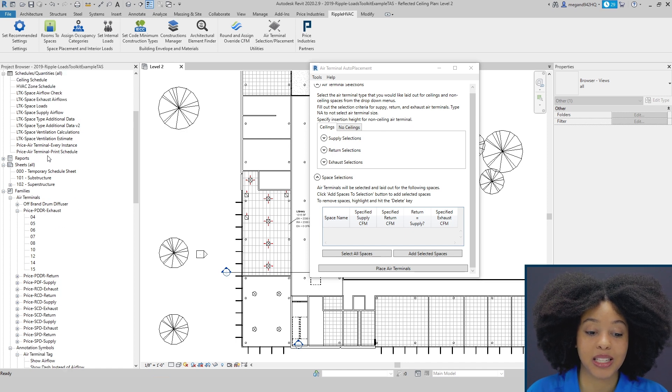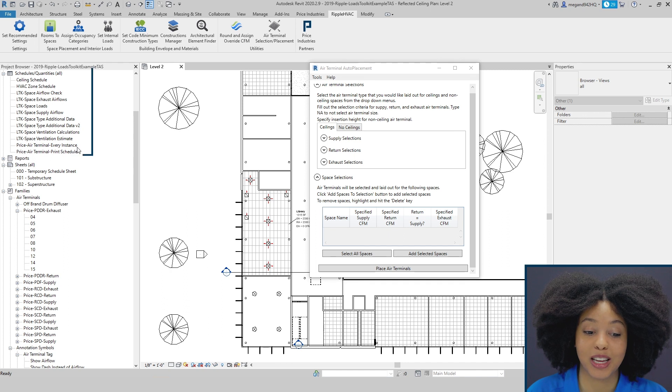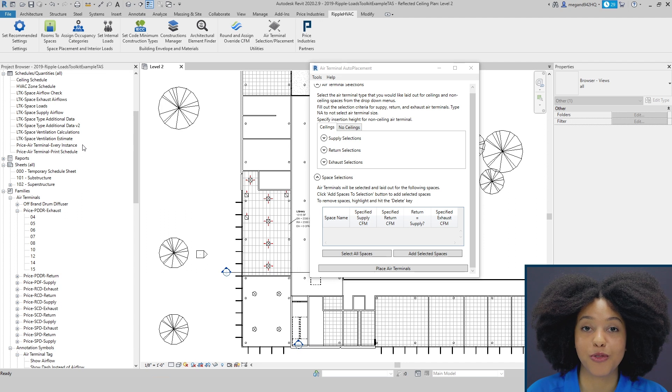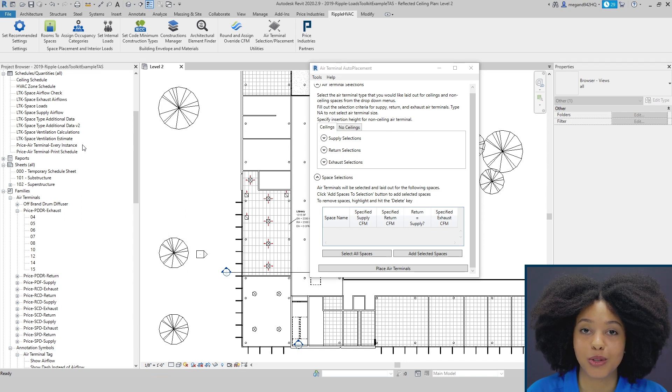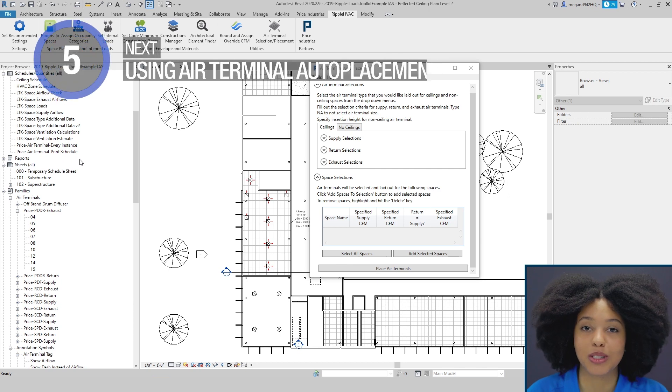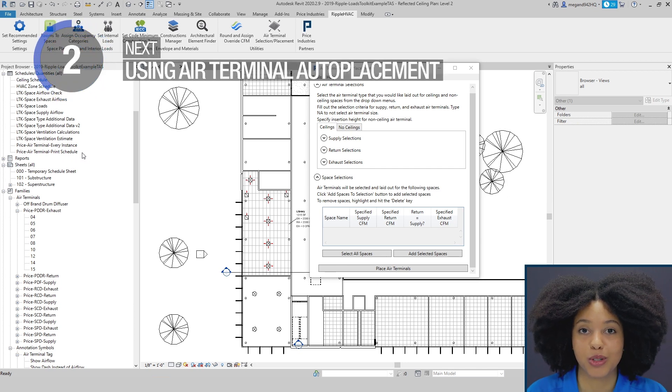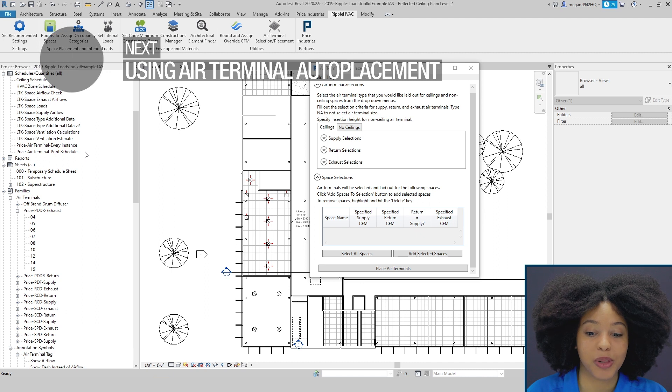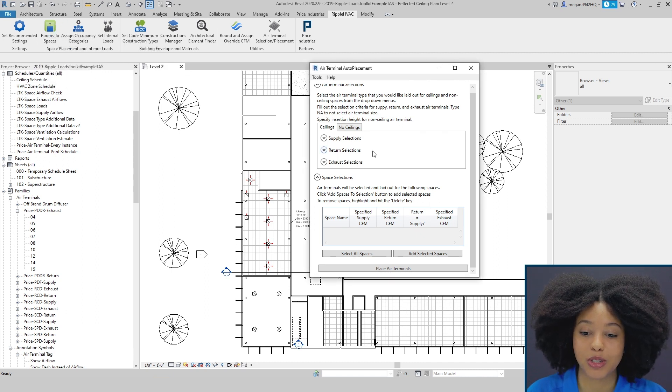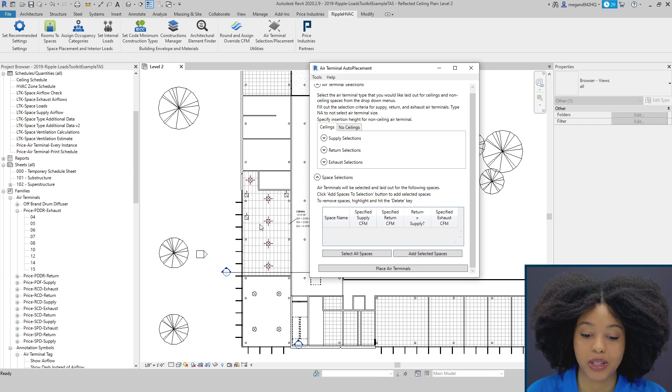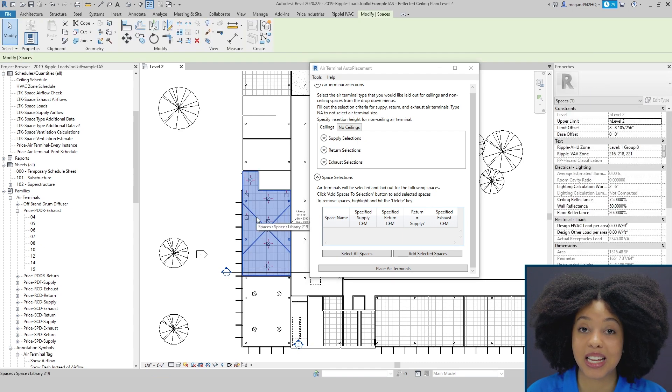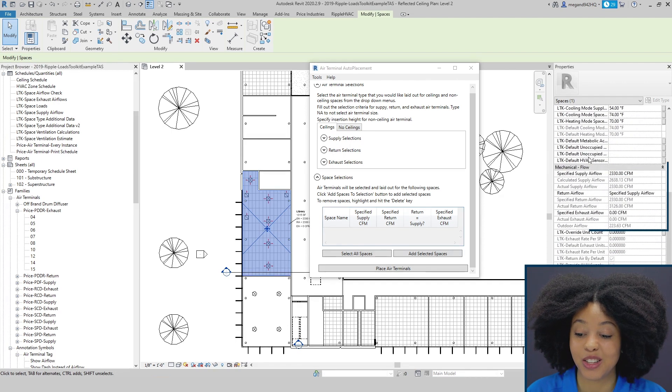The last piece is your schedules. It will import an Every Instance Schedule that will include information about every single diffuser in your project, as well as a print schedule, which is a more consolidated version that is more typical to what you would see on your plans. In order for the tool to place diffusers within your space, it simply needs two inputs. The first is it needs a space, and the second is it needs your air flows.